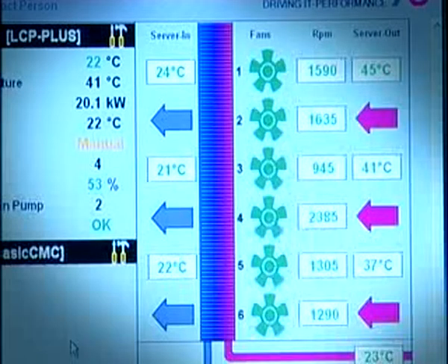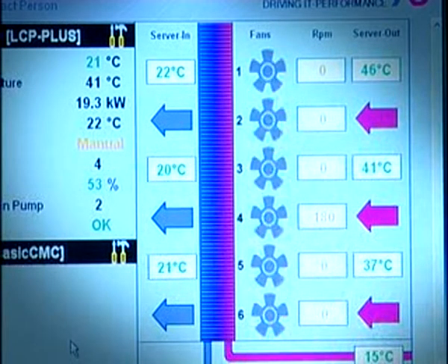N+1 configuration is very simple to implement, and in the unlikely event of an LCP failure, the secondary LCP is always available. To increase the robustness of the system even further, each LCP can be fed from a separate water supply, so even if the chiller fails, there is a backup supply.